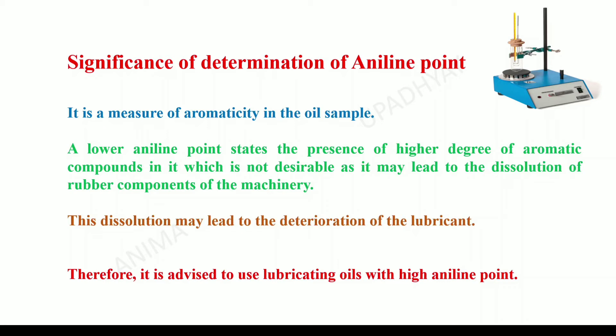If such a lubricant with high aromaticity — that is, low aniline point — is applied to machines having rubber parts, then these rubber parts will get dissolved in the lubricating oil. The lubricating oil will then lose its lubricating property and get deteriorated due to the dissolution of rubber into it. It will also reduce the life span of the machinery. Therefore, determination of aniline point is extremely important before applying any lubricant to a machine, especially if it has parts made up of rubber, parts coated with rubber, or if the gaskets or seals are made up of rubber.